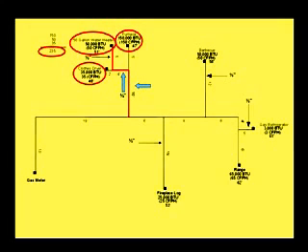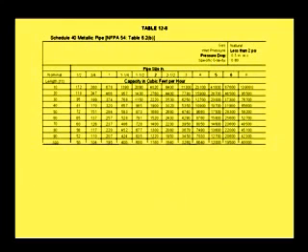The next 10-foot section of pipe will be supplying the branch line to the furnace with a demand of 150 cubic feet per hour, plus the 85 cubic feet per hour from the previous section, for a total of 235 cubic feet per hour. Refer to table 12-8, 60-foot row — 235 will fit under 257 — and see that a 1-inch pipe will accommodate the 235 cubic feet per hour demand for the 10-foot section.